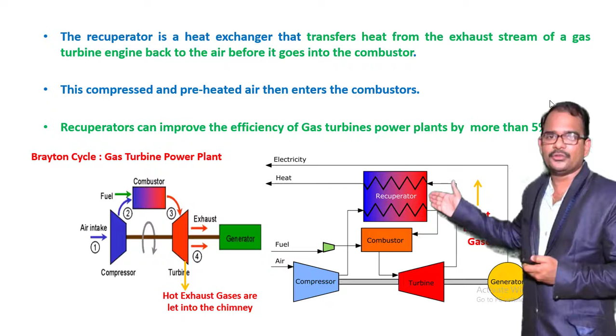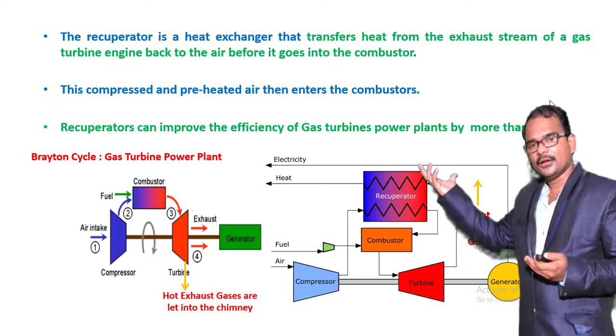To be frank, the waste heat is recovered here. The heat that would otherwise be wasted is now recovered by means of this recuperator, and thereby the efficiency of the system increases. Whenever efficiency increases, the amount of fuel sent into the combustion chamber decreases, and thereby pollution also decreases. This is the concept of recuperator waste heat recovery technology.